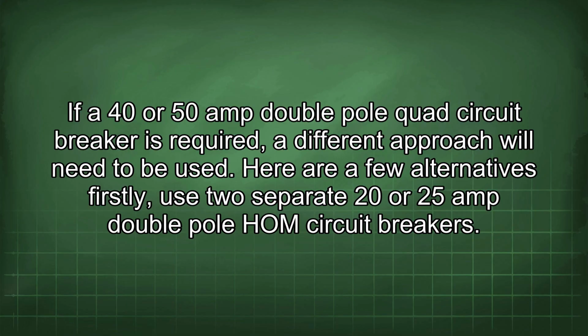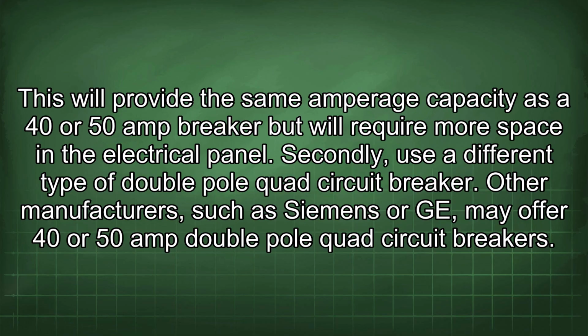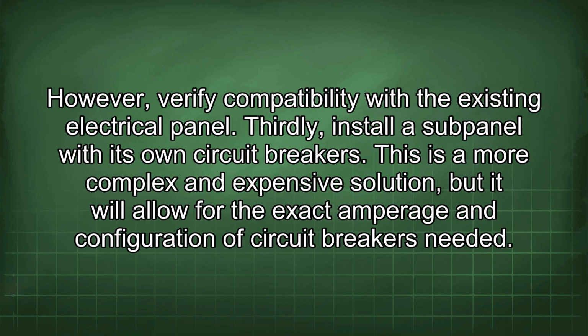Firstly, use two separate 20 or 25 amp double pole HOM circuit breakers. This will provide the same amperage capacity as a 40 or 50 amp breaker, but will require more space in the electrical panel. Secondly, use a different type of double pole quad circuit breaker. Other manufacturers, such as Siemens or GE, may offer 40 or 50 amp double pole quad circuit breakers. However, verify compatibility with the existing electrical panel.